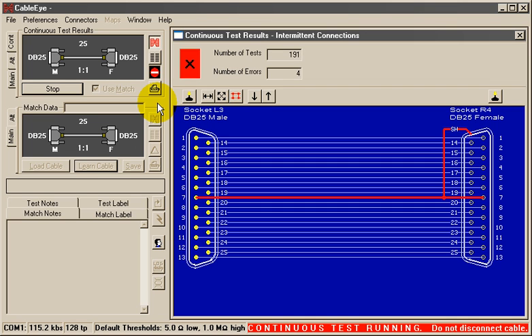The tone sounds every time the test data differs from the match data. In this case, pin 7 on the right connector intermittently shorts to the shield when the right connector is flexed.